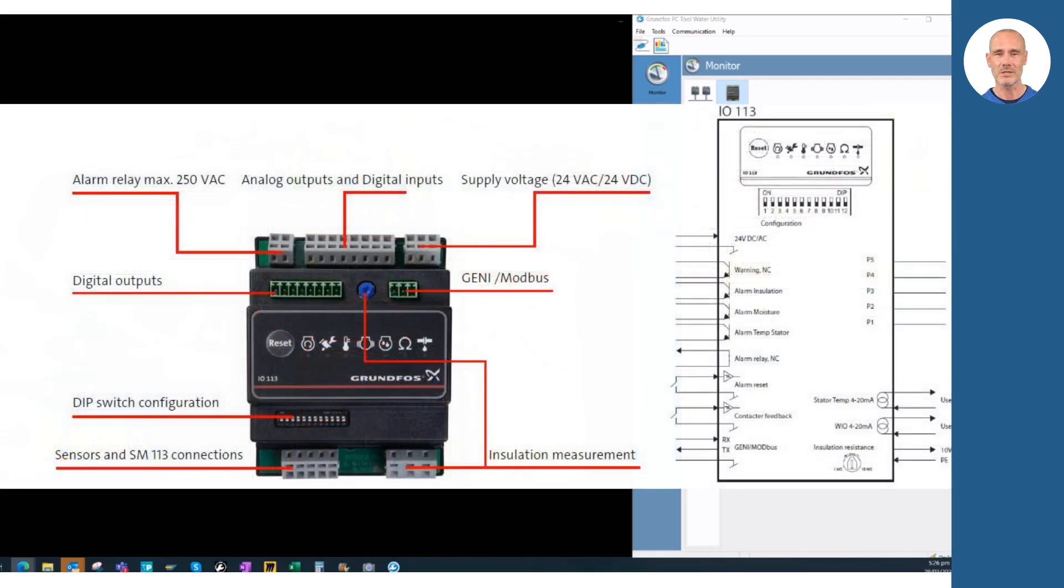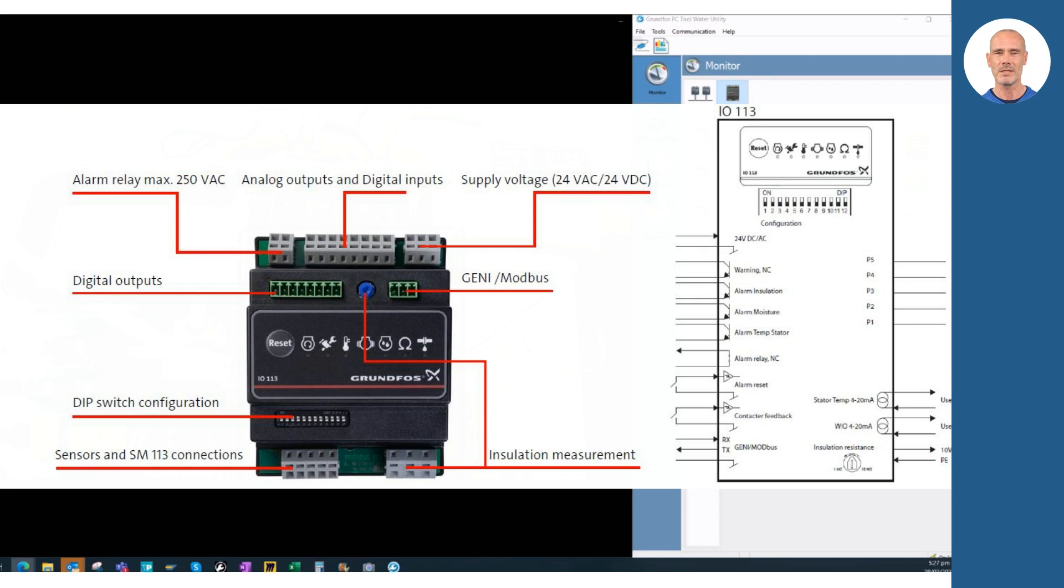In the image, you will see the inputs and outputs in IO-113. Apart from alarm and warning digital outputs, you will find analog outputs to transmit the status of the water in the oil sensor and the stator temperature.